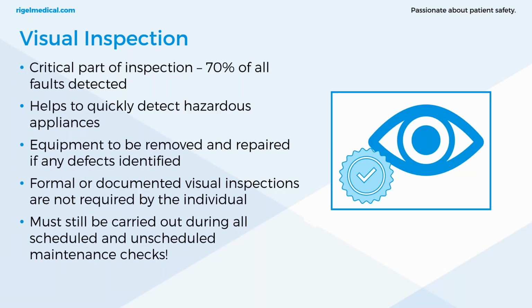Now in NFPA 99, there are no formal or documented visual inspections that are required by the individual. But that being said, a checklist wouldn't hurt. It'd be handy to have one within the workshop. Within some of our electrical safety analyzers, we do have a visual test check at the beginning of the test sequence. I'll quite often add that in as part of a test sequence, just as a reminder before an electrical safety test that all the visual checks have been made.